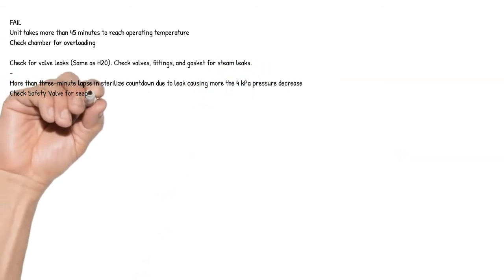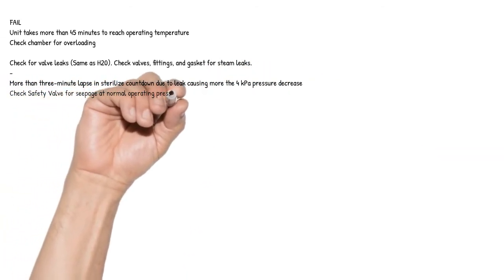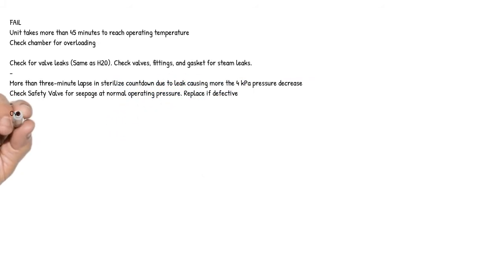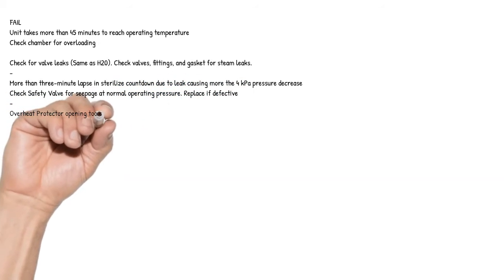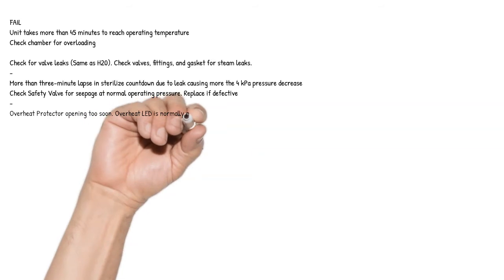Check safety valve for seepage at normal operating pressure. Replace if defective. Overheat protector opening too soon. Overheat LED is normally never illuminated.